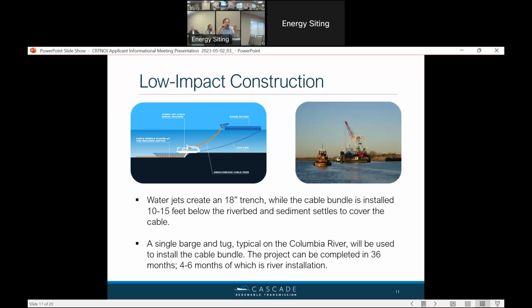So it's a slow, carefully monitored process. We've got data coming off the hydroplow, which is down on the riverbed, often called a sled. As that sled is moving forward, it's emulsifying the sediments. The cable comes out the bottom of the stinger and goes right into the bottom of the trench, and as we go past, the sediments come out of emulsion and go right back into the trench. So it's a simultaneous lay burial operation done almost as soon as we're there.